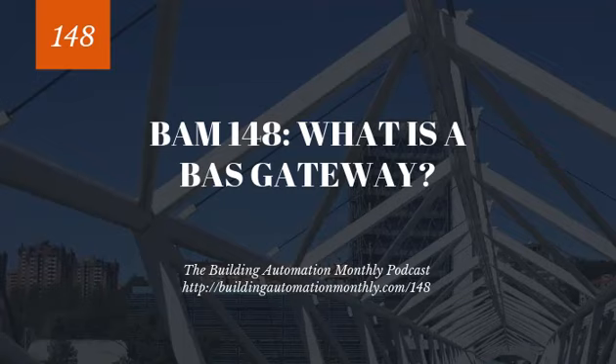No, not right. You see, protocol gateways usually require design and point mapping. If you've seen FieldServer or BabelBuster, or heck, even JACEs, they require some design and point mapping in order for you to take points and then share those points out a different protocol. Now, protocol gateways, as I mentioned, are the most common gateway. They can extend or normalize protocols, but their purpose is primarily to do protocol switching and not protocol normalization.